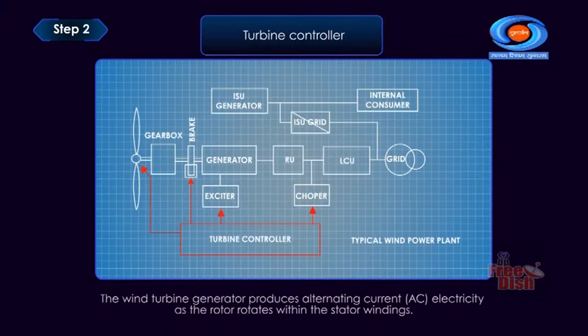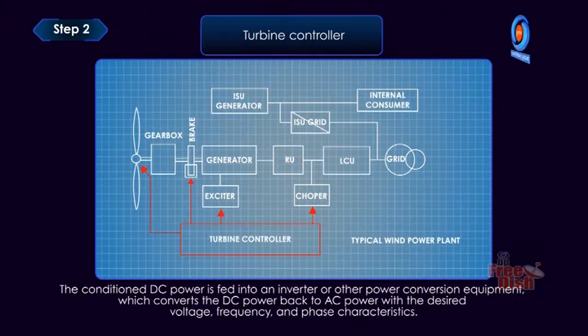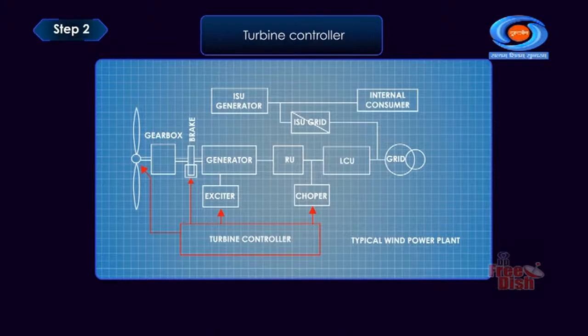Turbine controller. The wind turbine generator produces alternating current AC electricity as the rotor rotates within the stator windings. The AC output from the generator may have varying voltage and frequency depending on wind conditions and turbine speed. The conditioned DC power is fed into an inverter or other power conversion equipment, which converts the DC power back to AC power with the desired voltage, frequency and phase characteristics. The AC power is then synchronized with the grid and transmitted for distribution to consumers.